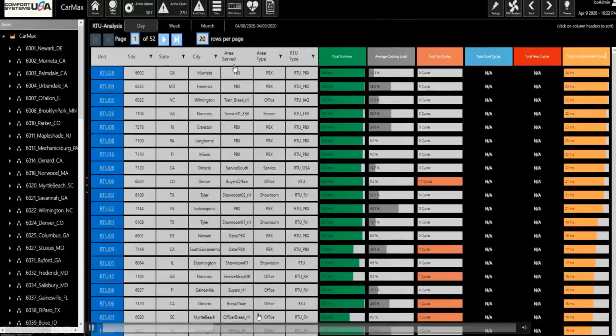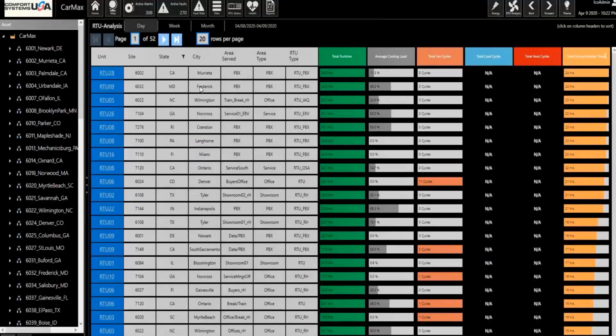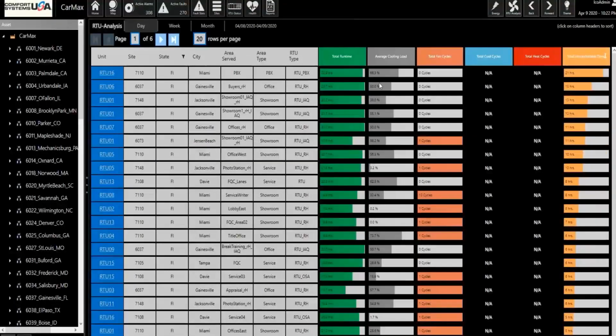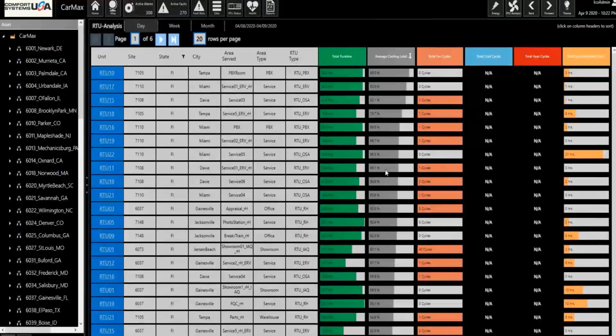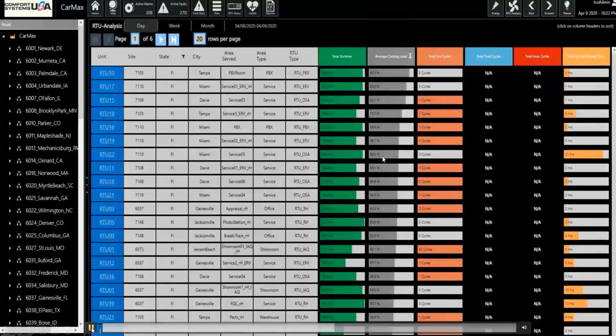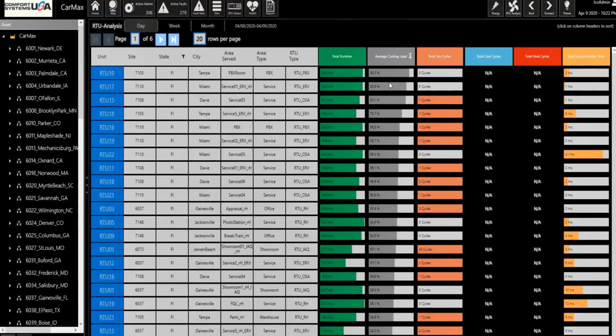I'm going to narrow down and just look at all rooftops installed on buildings in Florida. All of these should generally be at the same outdoor air temperature, but in this case I sorted by average cooling load, the actual percentage of time compressors are running on those units. So it brings up the question: why do I have certain rooftops where the compressor is running 90% of the time? This is about providing insights so smart building engineers can quickly identify problems and abnormalities.